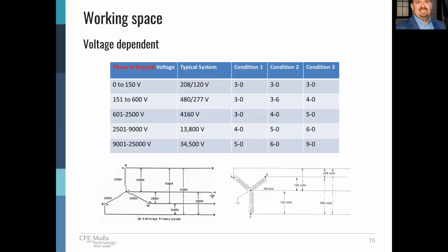So we talked about the depth of the working clearance being dependent on a couple of factors. It's very much voltage dependent. So if you look at the system voltages, we can reference back to the tables in the NEC. This gives us an understanding of what the working clearance depth needs to be. It's also contingent upon 3 operational conditions. These conditions speak to how the electrical space is laid out, what is directly across from our equipment.